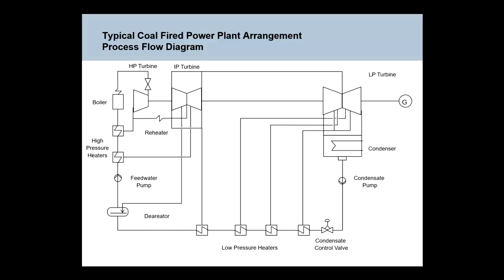The other thing I find interesting is to give you a feel for the energy level of this steam. If you have a pinhole leak in the wall of the boiler, and I've got steam at 20 megapascals and 600 degrees C, the first thing you would sense is an ear-piercing scream, because that steam is coming out at supersonic speeds. There would be a cloud of water vapor somewhere over here, and if you walk through the superheated steam jet that's coming out, you would be vaporized. Okay, so this is really high energy stuff that we're talking about.